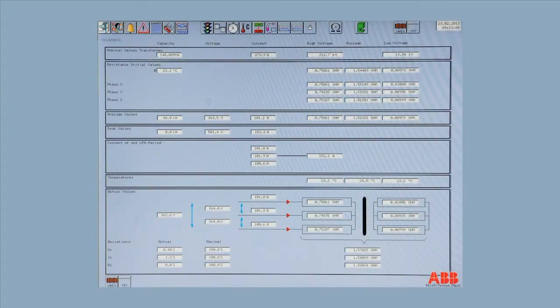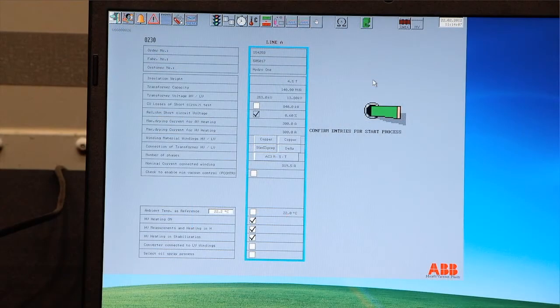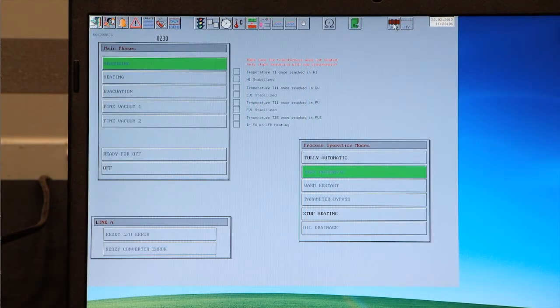Overview. Measuring. The measuring phase is measuring the initial resistance of the windings and assigning the starting temperature to the measured values. This resistance will then be used as a reference value for all temperature calculations throughout the entire process. When the transformer data has been entered and confirmed, and all parameters have been entered, the process can be started. This is done by clicking on Measuring in the phase screen.